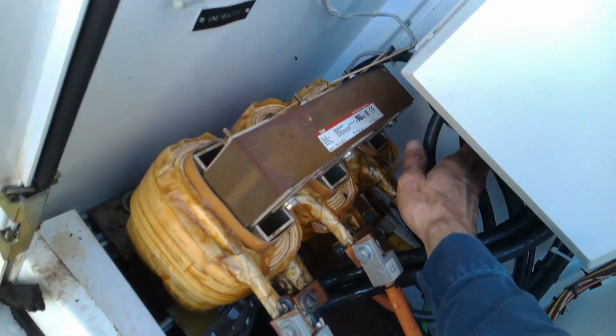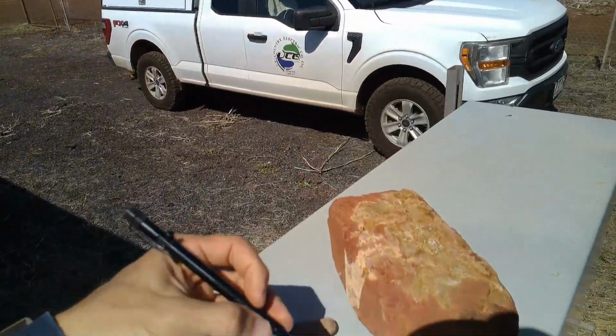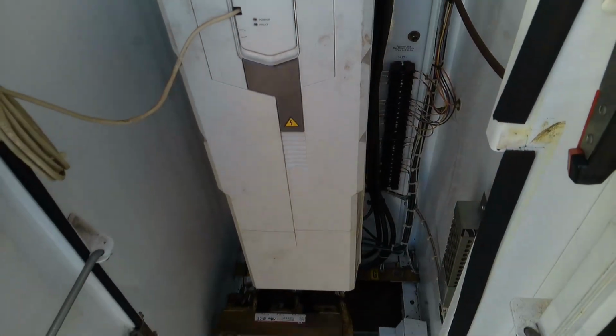So terminals L1, L2, and L3 are wired to incoming power. L1, L2, and L3 are wired to incoming power. And terminals T1, T2, T3 are wired into drive incoming power. Good. Yes. Yes, we might as well do all this stuff on pump 1 as well, even though oddly it's been working. Whew, cooking in here.